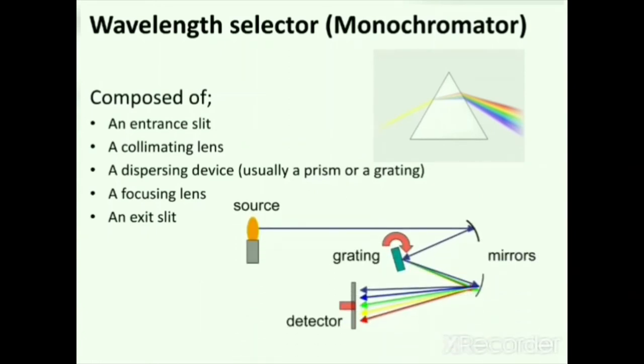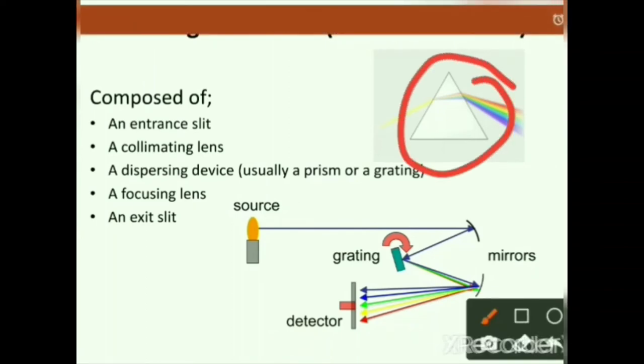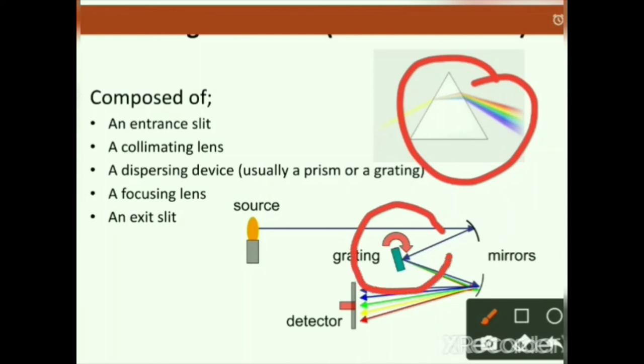The wavelength selector, also known as the monochromator, is composed of an entrance slit, a collimating lens, a dispersing device, a focusing lens, and an exit slit. Dispersing devices are of two types: prism and grating. Prisms are made of glass, quartz, or silica — though glass is avoided because it absorbs electromagnetic radiation. Gratings are made of aluminum, and the dispersing power of a grating is greater than that of a prism.